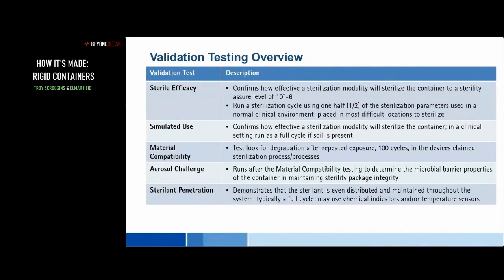The other key thing about this cycle is that it's a half cycle. In the case of a steam sterilizer, instead of a 4-minute cycle, it's actually a 2-minute cycle. It's placed in the most difficult spot in the sterilizer. So it's basically the worst case scenario, showing that you can still achieve sterility assurance.